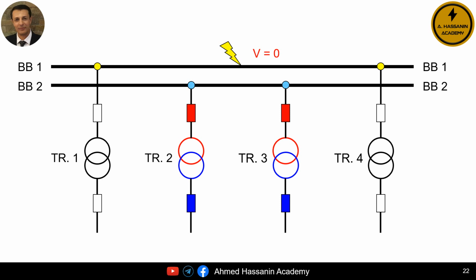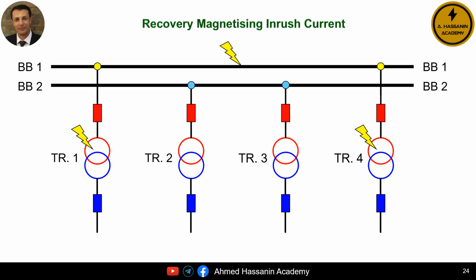This of course means that the voltage on bus bar number 1 will drop to 0 for a short period of time, after which the voltage on bus bar number 1 will return to its normal value, and all of this happens within a very short time period. Naturally, the fact that the voltage disappears or drops to 0 on bus bar number 1 and then returns again means that we have essentially performed a re-energization of transformers number 1 and 4. And as long as the transformers have been re-energized, then of course it is very likely that a magnetizing inrush current may occur due to the disconnection and subsequent reconnection of the transformers. And the magnetizing inrush current in this case is called the recovery magnetizing inrush current.